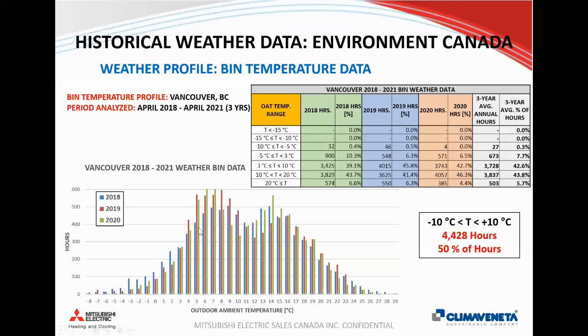So this is a bin hour histogram, basically. On the left axis for Vancouver, this just shows you the amount of hours that you're spending at any given temperature. So for example, if you look at the green lines, this is actually 2020 data, but for 6 degrees Celsius outside air temperature, there's 600 hours in a year that you spend at that temperature. If you look at the amount of time where it's below -15 for Vancouver, you'll see that it doesn't get below -8. So if you're using a heat pump technology, you don't necessarily need to worry about an auxiliary heat source. And in fact, what we're seeing in British Columbia is that they're eliminating natural gas boilers from the building, and in some cases they won't even have a backup boiler.